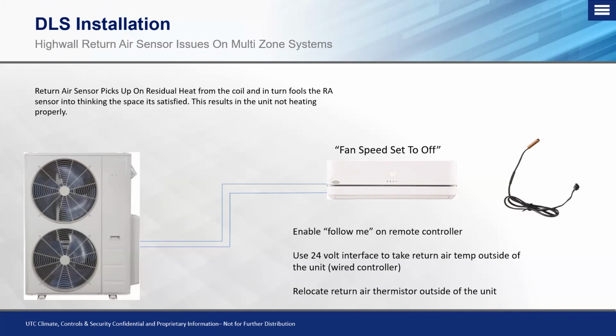Another thing that we can do on these is we can enable the follow me mode on the remote controller. Now, I'll be 100% honest with you, the follow me mode hasn't been the most consistent mode. So this is usually something that I'll do with you when we're troubleshooting to confirm that the system actually is picking up on residual heat, which would have to have us relocate that return air thermistor and shut the fan speed off after set point. So you can think of the follow me as a temporary solution until you can relocate that return air thermistor.